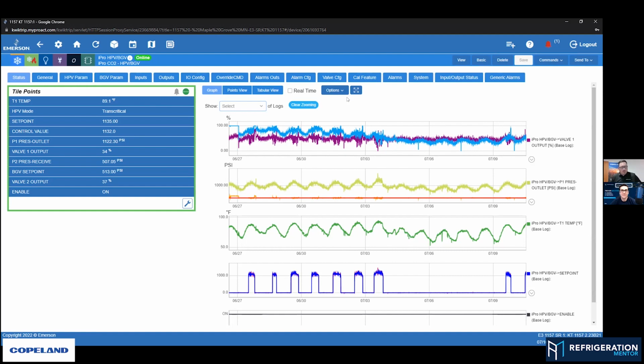And now in transcritical CO2, we've taken that to a next level, and now some people call it the magic valve or the voodoo valve or the pressure drop valve. There's a lot of names that people have coined here, but the valve's intent is to create a pressure drop so that we can get liquid into the liquid vessel or liquid receiver, as some people still call it. And by that, I mean usable liquid too, right?